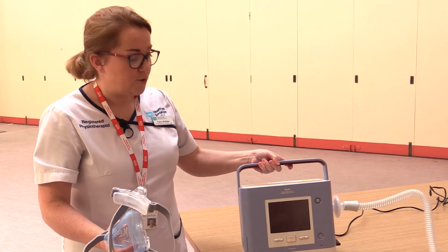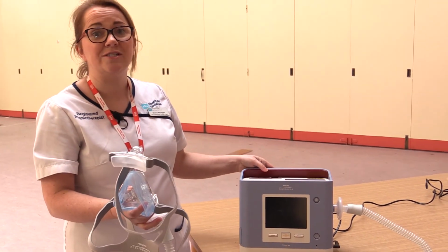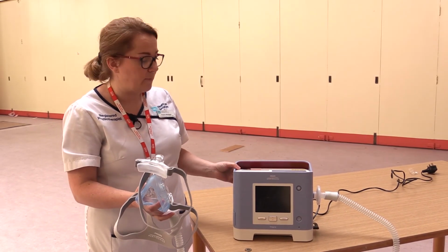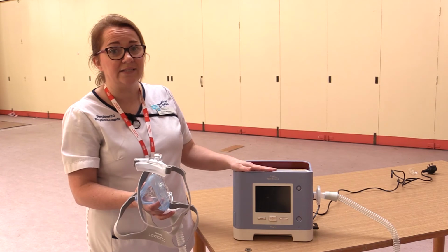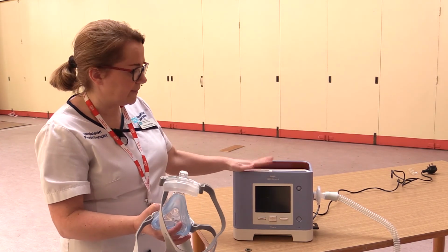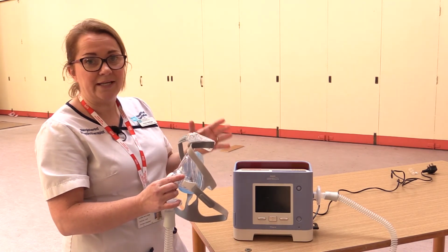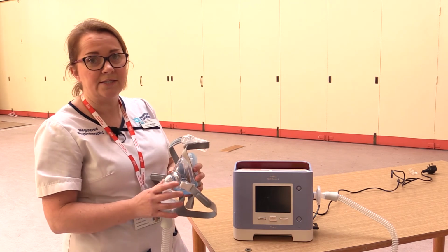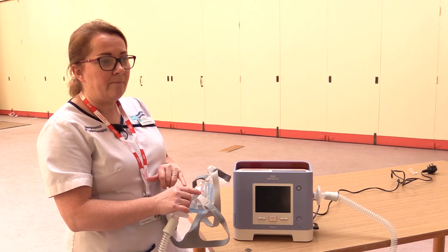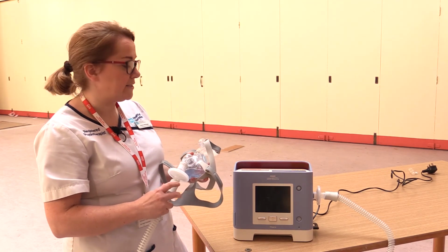Okay. So this is the Trilogy 100, and this is the machine that is used in the hospital setting, and we also have a few patients in our community setting as well. This machine can offer full ventilation, but we use it for non-invasive ventilation within the hospital in an acutely ill patient. The main differences, as already alluded to, is the fact that the circuits usually have a full face mask with our patients, and they're non-vented masks because we have an exhalation port within the system.